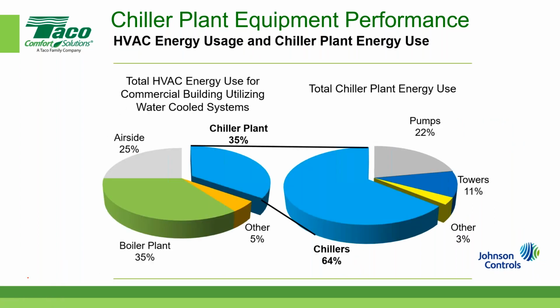All right. And out of that 38%, the chiller plant, and you can tell right here, the chiller plant's about 35%. The boiler plant is also about 35%, but that number varies. Especially in the United States, if you move closer to the south, that chiller plant percentage goes up and the boiler plant percentage goes down. So even though in terms of overall averages, the chiller plant is actually probably the dominant energy user. And of that 35%, the chillers make up roughly 64%.